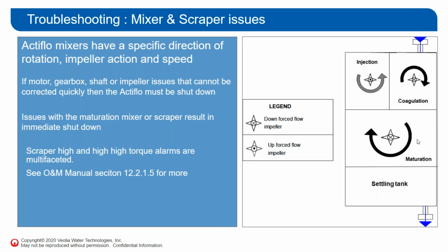Not only because it will help to shear your floc less if it's in your injection chamber or your maturation chamber, but because it's going to affect that retention time that's so important, where what I was talking about, the water chemistry, all of those slides ago. Either you're going to short circuit, or you're going to cause too much precipitation in the sides of your tanks.